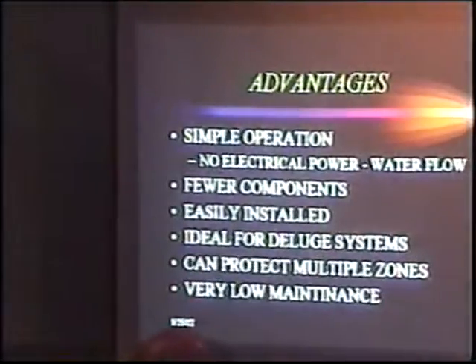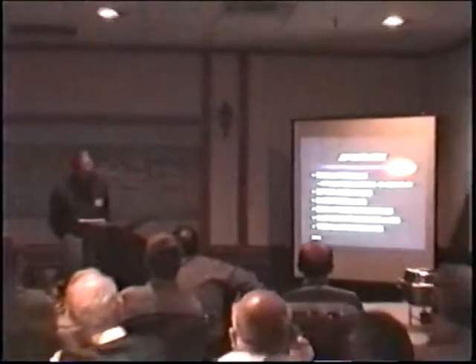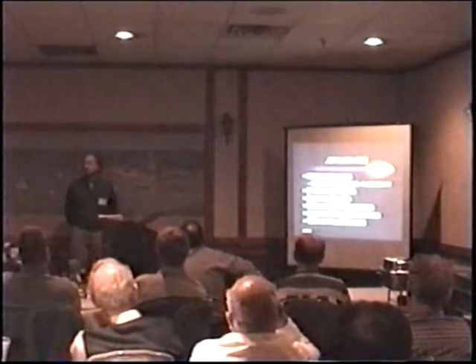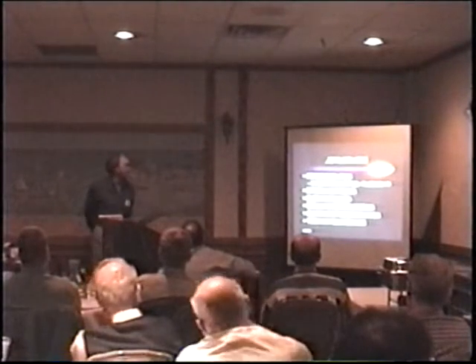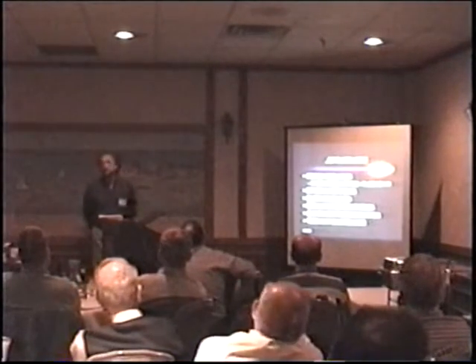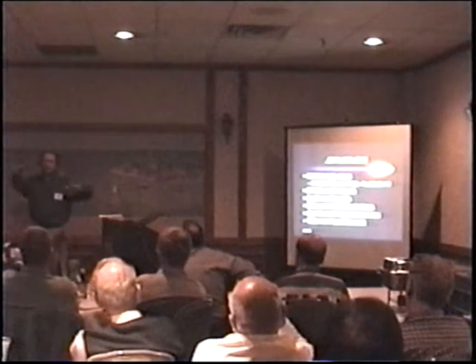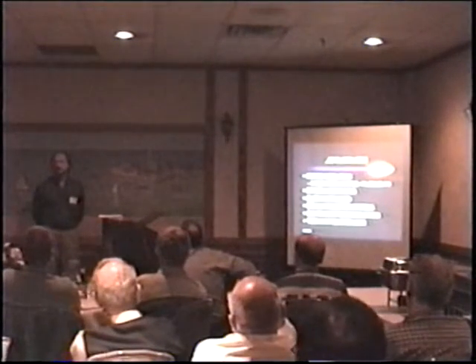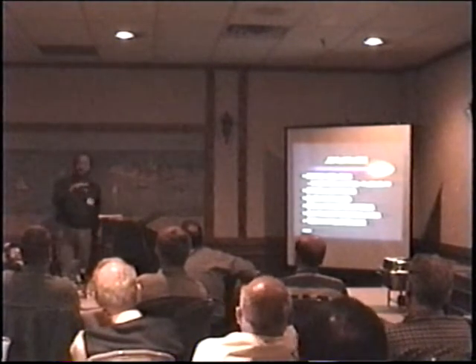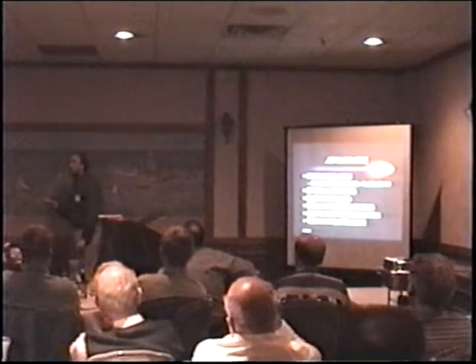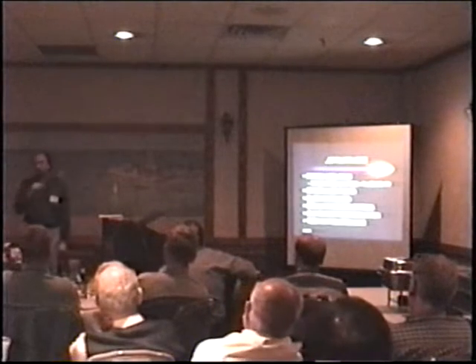Back in the late 70s, early 80s, and throughout the 80s, we were doing a lot of these. All the systems that we were doing were deluge systems. And that trend has changed a little bit now. You can protect multiple zones. You size that system for the largest single hazard, so you can have 5, 6, 7, 8 risers going to 8 different zones. And the tank is sized to handle the biggest riser or hazard. And you'll have these multiple control valves, and whichever system dumps, that valve opens to that particular control.